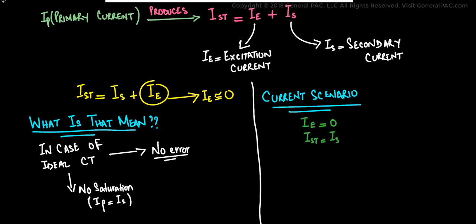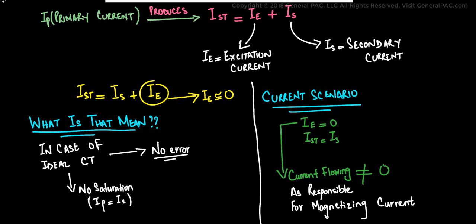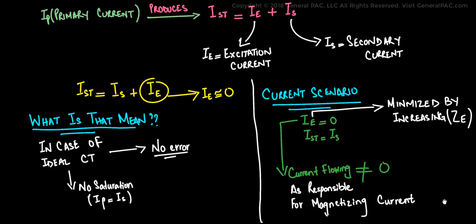IE is zero or it is a negligible value. So practically speaking, IE, the current flowing through the magnetization branch, cannot equal zero because it is responsible for producing the magnetizing current in a current transformer. And that is required for it to operate in a practical sense. But it can be minimized by increasing the value of the excitation impedance.